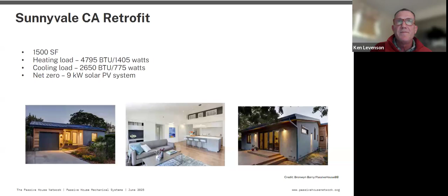With the equipment in this house, they do have a direct vent hood, but it's not a high-powered one—it's an induction cooktop. So we can throw the system out of balance for a short period of time and not take a huge hit; we'll just calculate that into the energy model. But again, we don't want a huge industrial exhaust hood there without makeup air. We've got indoor heat pump hot water heater—there's enough space, enough consideration to make that work and not have it interfere.